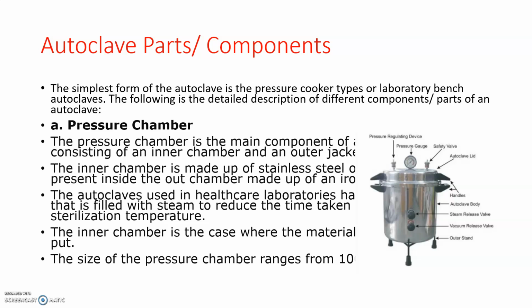Next we are going to discuss the detailed description of different components or parts of an autoclave. First one is the pressure chamber. The pressure chamber is the main component of the autoclave, and it consists of an inner chamber and an outer jacket. The inner chamber is made up of stainless steel, and it is present inside the outer chamber made up of iron. The autoclave used in healthcare laboratories is filled with steam to reduce the time taken to reach the sterilization temperature. Okay, so the first important part is the pressure chamber.